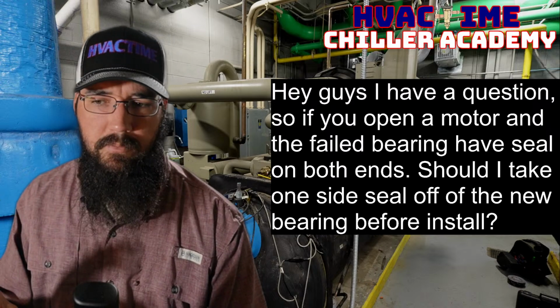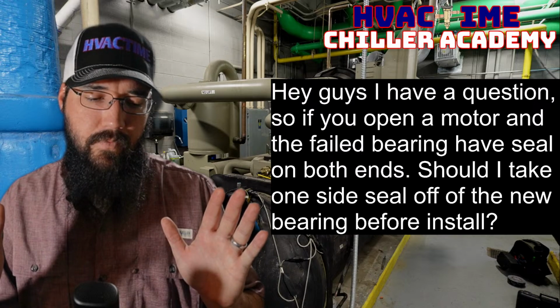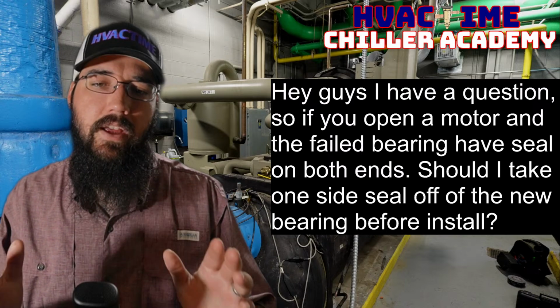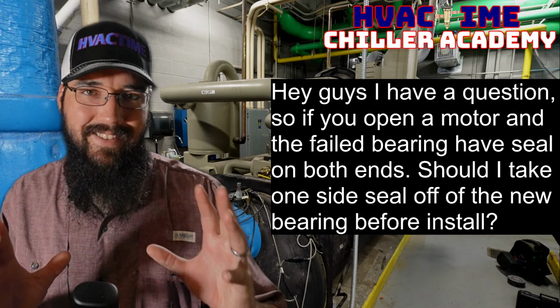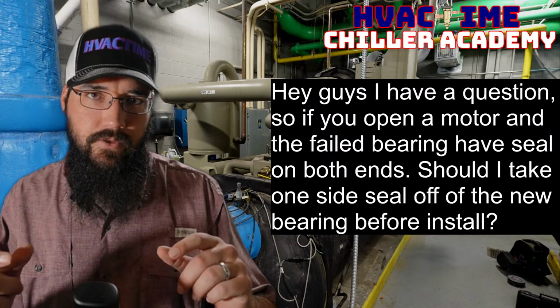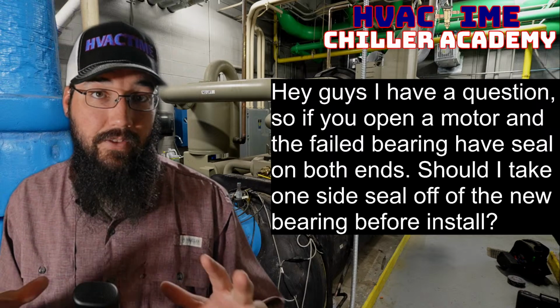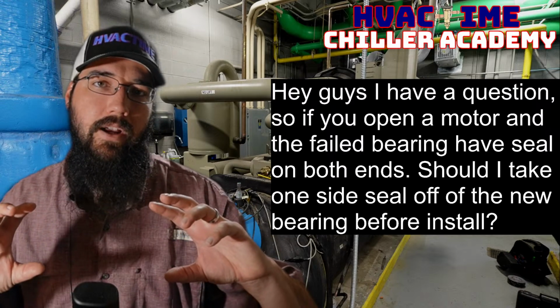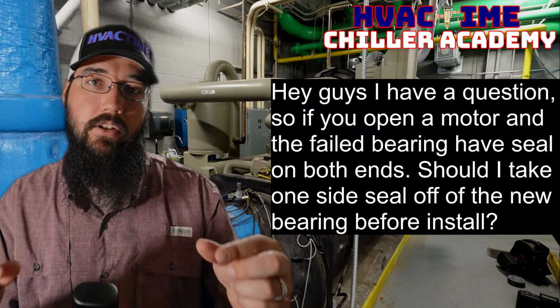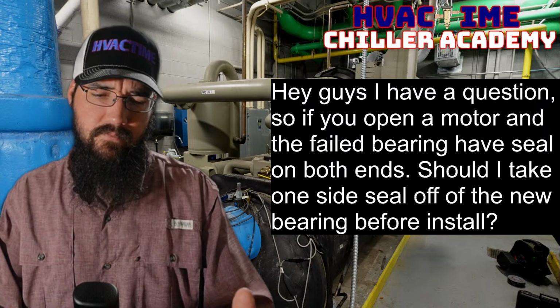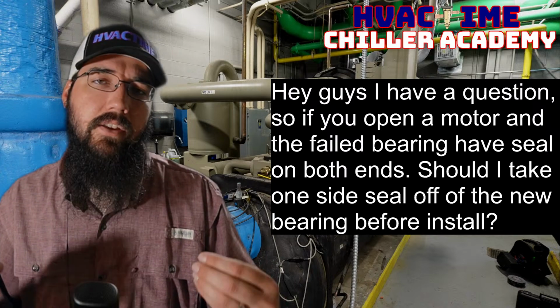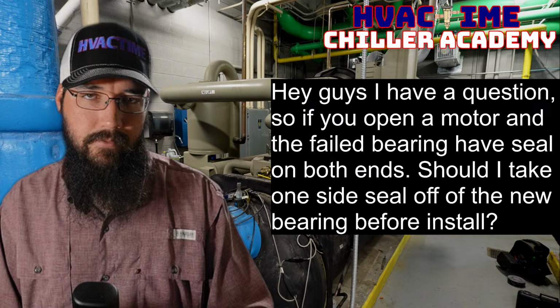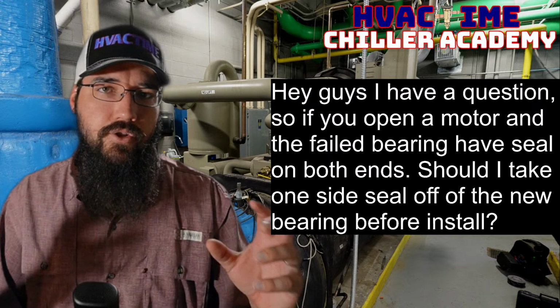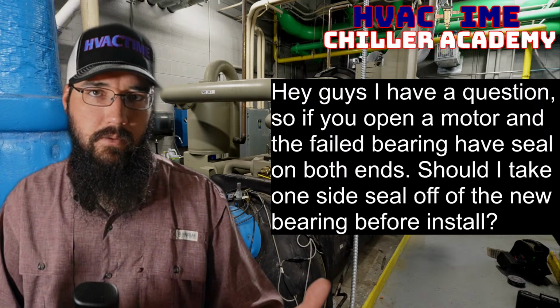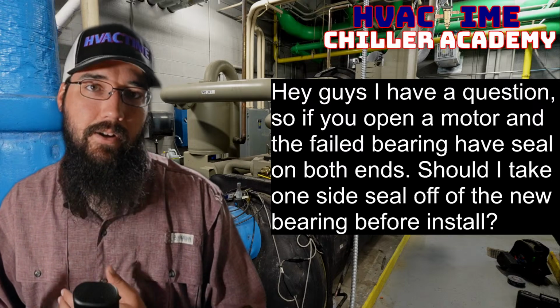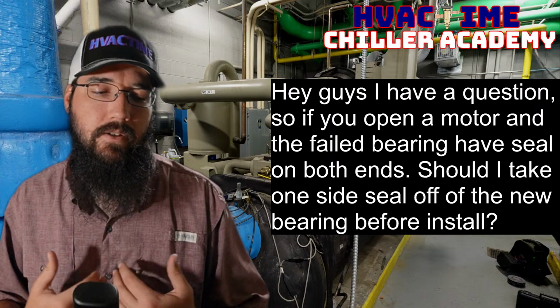So the bearings themselves have shields on them. Okay, so in your particular case, if there's a difference between sealed and shielded. Shields don't have any kind of sealing material around the edges of the race, where a sealed bearing will. It looks different on the race itself, and it should be identified on the bearing packaging. So even if the original motor was truly a sealed bearing, as long as you have a grease housing and grease ports that you can grease the motor with, converting that to a greased bearing or a standard bearing isn't going to be a problem in my experience. I've had to do that plenty of times.